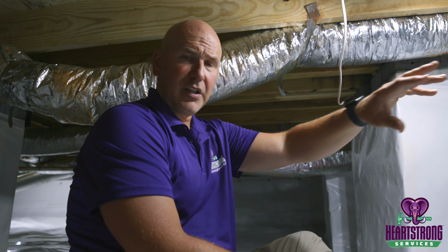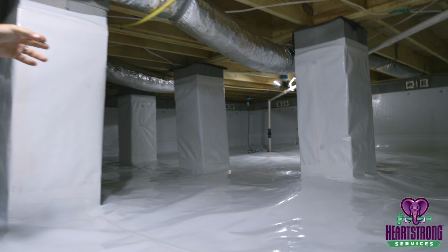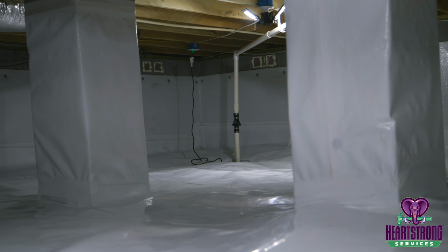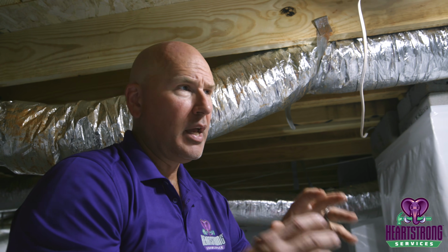Then to deal with the standing water problem, you saw in the video where we dug that trench all along the footer inside of this crawl space. We installed that drainage pipe, and then we pitched it down to a sump basin and sump pump that we've installed. That's what's now over here in this far corner across from me in the background, and we'll have some better footage of that in a minute. You'll be able to see that all of that water is now being actively collected instead of passively collected like it was before, and it's being sent down to one location and then pumped and discharged underground and completely on the outside of the house, which is what's going to keep this space dry all the time, even during periods of heavy rain.